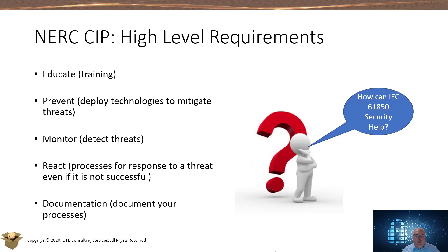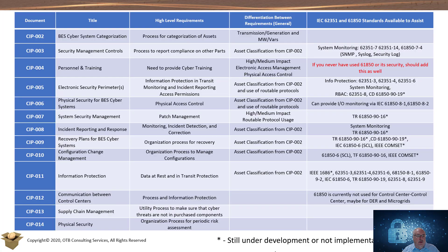So how can 61850 security help meet NERC CIP requirements? This table is very busy, but you can see there are many standards related to system monitoring. There are standards that assist in providing role-based access control, system monitoring, and data-in-transit protection for information that goes across an electronic security perimeter. As with most IEDs, they have the ability to monitor I/O and therefore can provide some help in monitoring physical asset access to the substations or the IED.